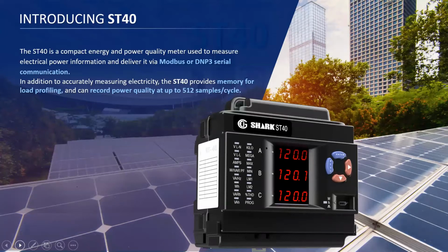So introducing the ST40, a really compact energy and power quality meter that can be used not just to measure your electrical power information, but also advanced power quality information, and then deliver it over Modbus or DNP serial communication. The real inspiration behind the design of the ST40 is its compact design for those tight spaces and machine monitoring level where you don't have a panel where you can actually put a panel meter in, but your apparatus, your equipment is really critical and you do want to get all of that information, not just for energy usage, but also power quality. This is really the perfect meter for those types of applications, for those tight spaces. It's got a very small footprint, but it will give you all of that powerful data that you will need.